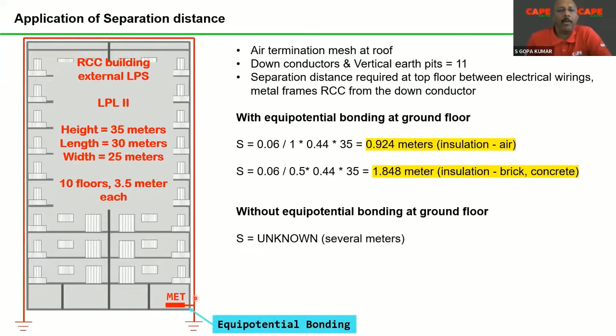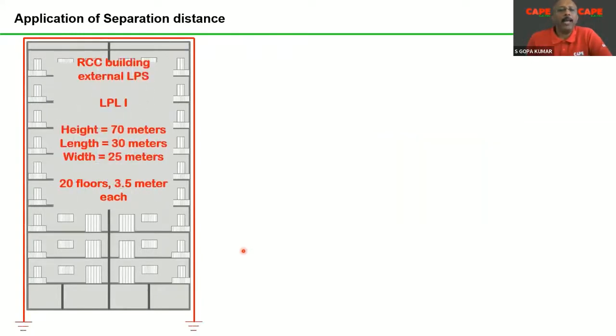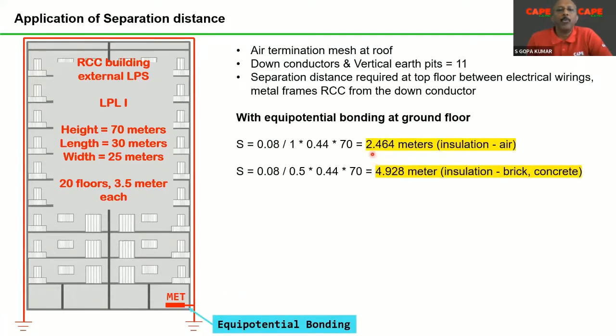In India, unfortunately, in a lot of buildings the equipotential bonding does not exist. Under that condition, please note that the separation distance would be very, very high. Practically, what can happen is there can be flashover at several points of the building. Now, I am making the same calculation for a building of height 70 meters, lightning protection level 1, a 20-floor building with 3.5 meters per floor, with equipotential bonding. Under that condition, the separation distances are 2.464 meters in air and 4.92, or about 5 meters, in brick.